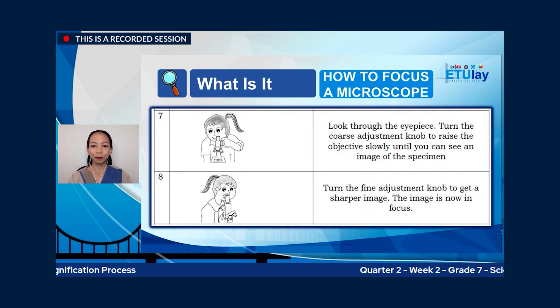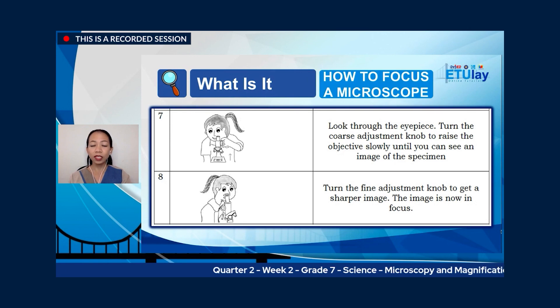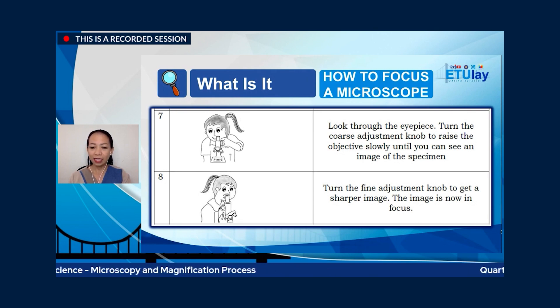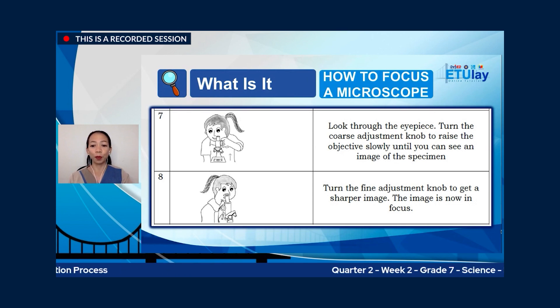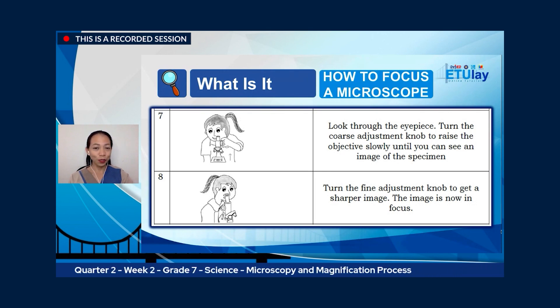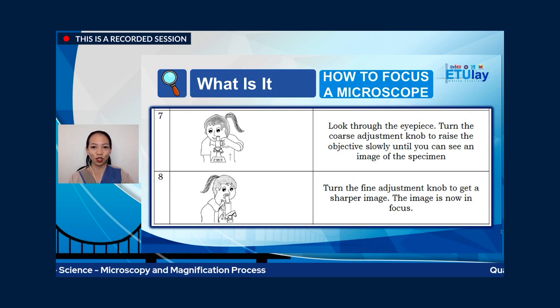Step seven: look through the eyepiece. Turn the coarse adjustment knob to raise the objective slowly until you can see an image of the specimen. Step eight: turn the fine adjustment knob to get a sharper image — the image is now in focus. Focusing a slide on a microscope takes patience, so resist the temptation to rush.